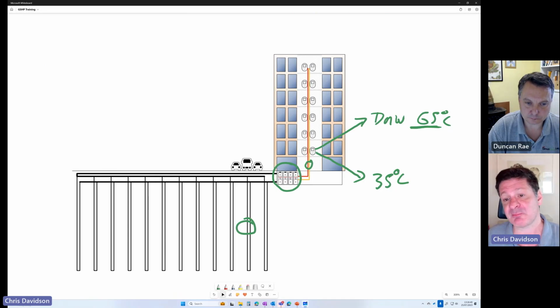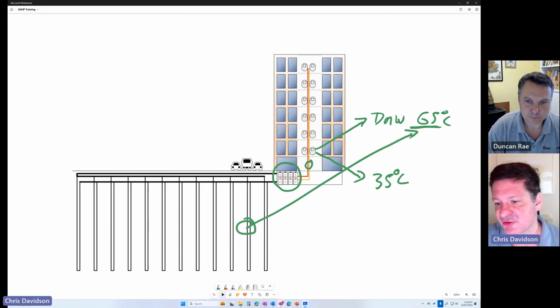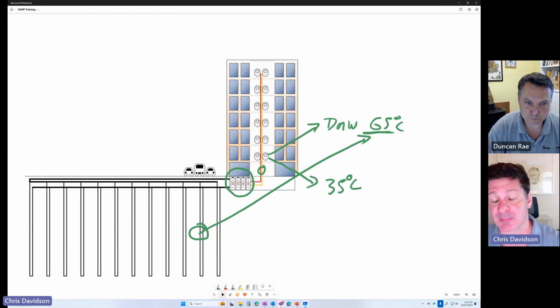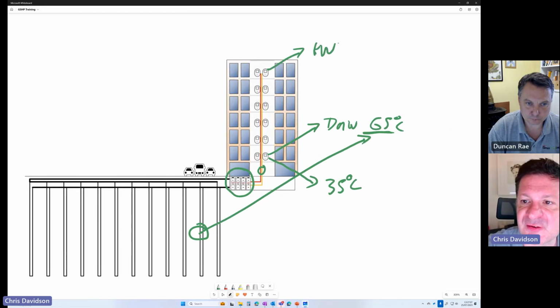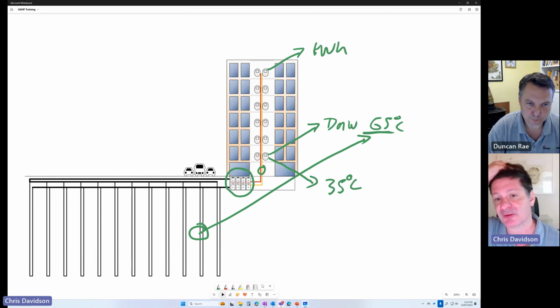I liken that to, say, climbing a small hill. We're going to use less energy than if we're climbing a big mountain. So what we're doing is compromising that space heating efficiency because we're running everything at that 65 degrees C. Another important point to make about these systems is that there'll be a sale of heat agreement associated with each kilowatt hour of heat delivered into that dwelling.